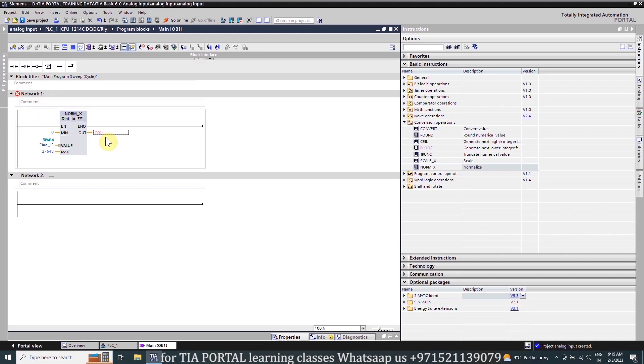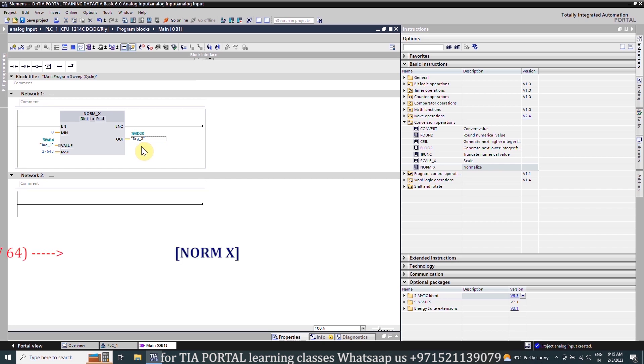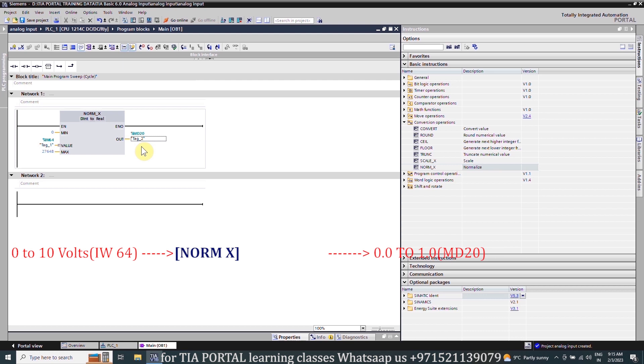Next for the output data type we will select the real, and in the output we will insert MD20. Now our NORM_X function will take the analog input which is coming into the input word IW64 and normalize it from 0 to 1, and save this normalized value into the MD20 data register.